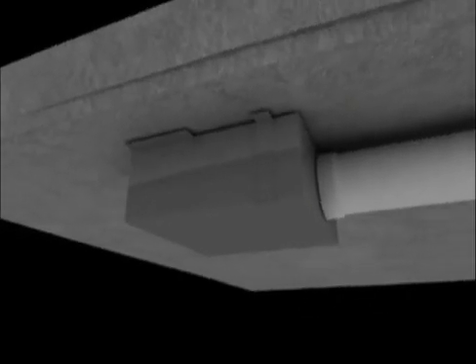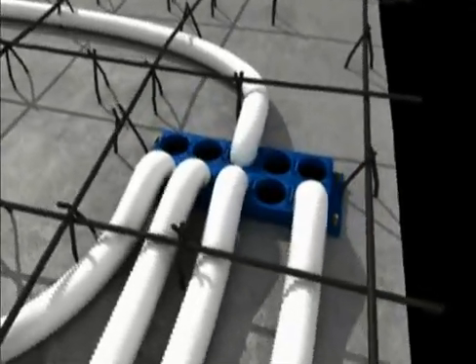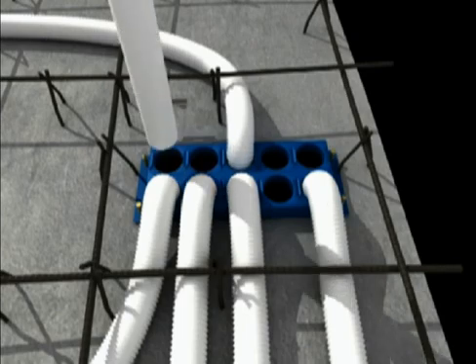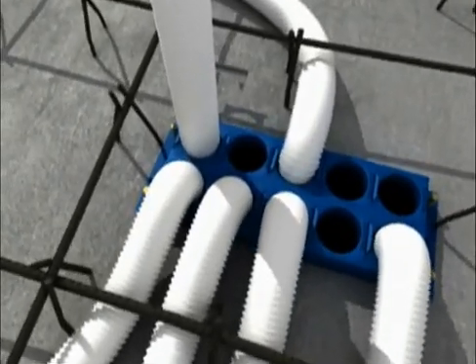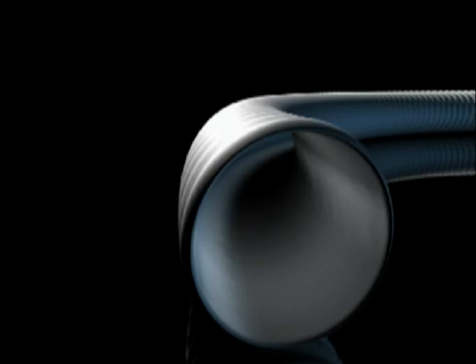The flexible and internally smooth ventilation tubes, known as Comfort Tube, consisting of odourless HDPE plastic, can be quickly and easily fitted between the reinforcements in the concrete, wooden floors and walls. The tubes are connected by the Comfort Fresh connection plate. The external tube profiling enables simple fixing by means of the patented fixing slide valves. Thorough cleaning is easy, since Comfort Tube has no junctions, angles or cross-sectional changes.